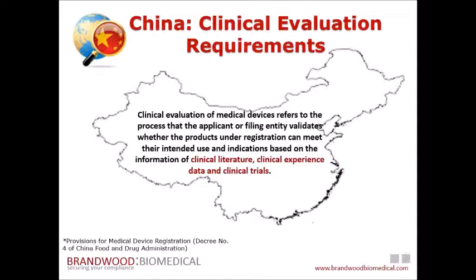But I'll go through, there are some local differences in China which don't exactly mirror what Europe and Australia have. So key local requirements. The first one is that clinical trial data must be done in China for Class 2 and Class 3 devices unless you can justify that they can be exempted. And I'll go through in a bit more detail later on. Clinical trial is not required for Class 1 or if the device is listed on the catalogue of devices exempted from clinical trial.